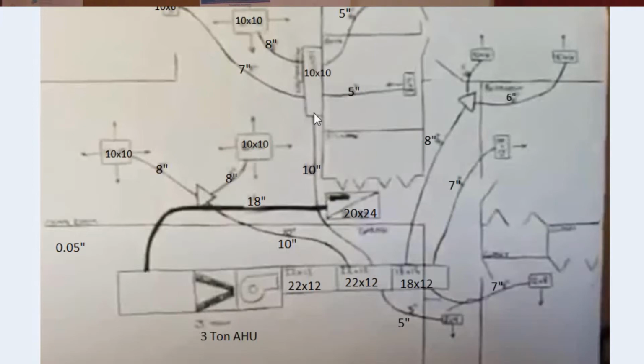So let's just say we've got 175 CFM hitting this box. Now we're going to take 175 CFM and divide that between 4 diffusers. We've got a 5-inch, a 5-inch, an 8-inch, and then a 7-inch. I guarantee most of that air is going to hit this 8-inch right here, and there will not be a whole heck of a lot left for this 7-inch guy here or any of these 5-inchers. So we're going to take that 175, divide it across those 4, and get maybe, let's just see, 40 to 60 CFM out of this one.